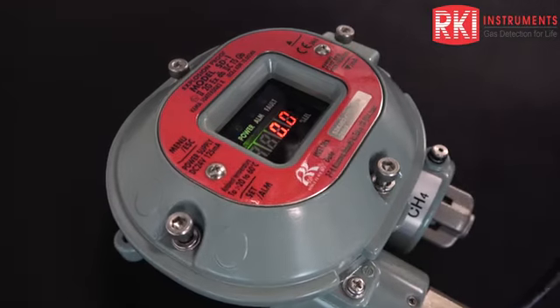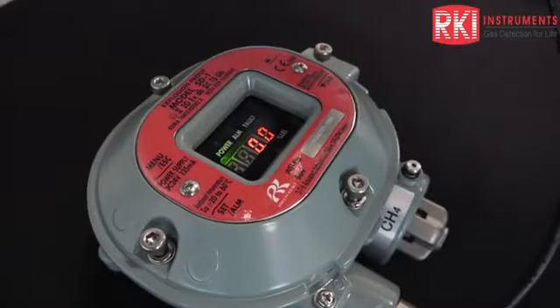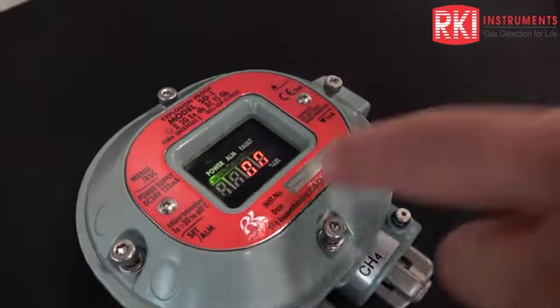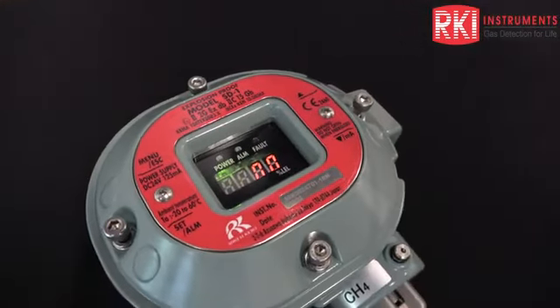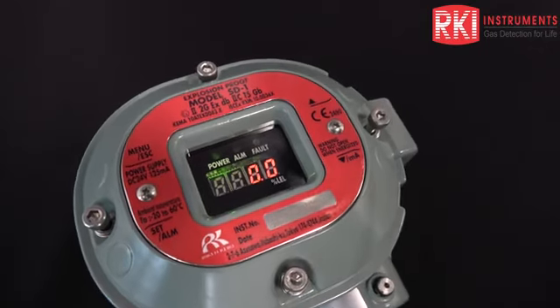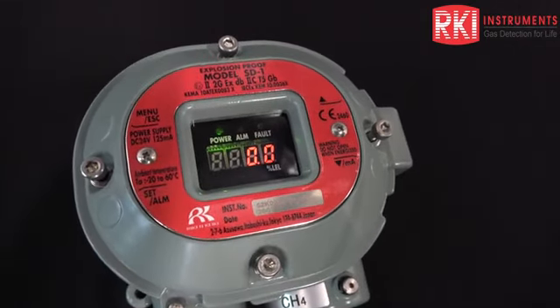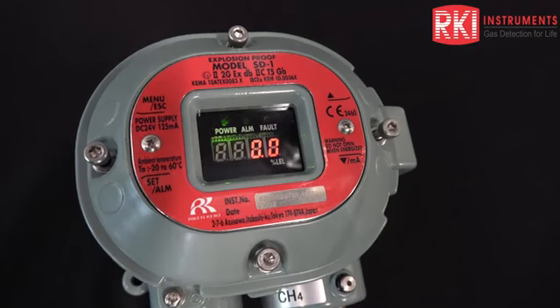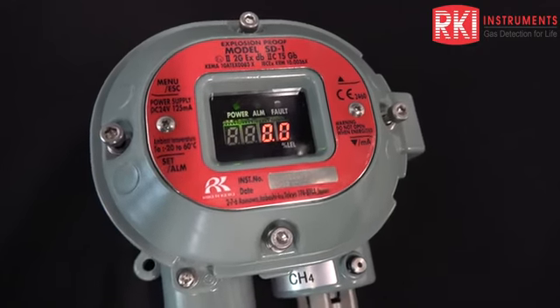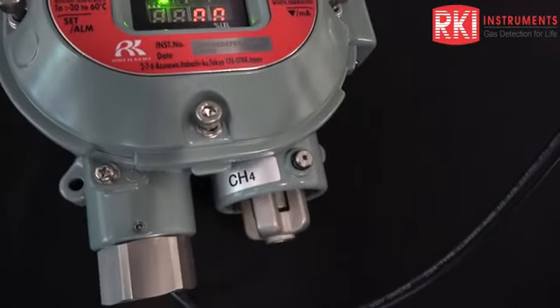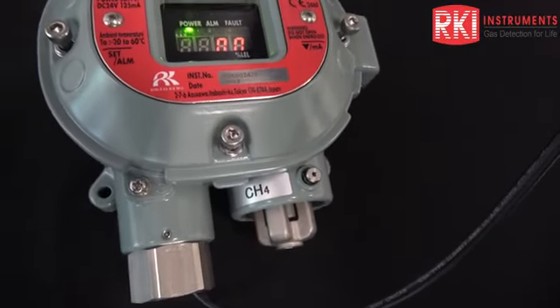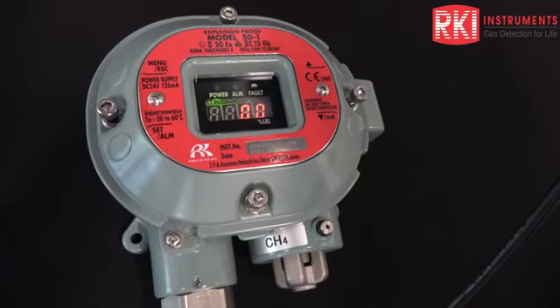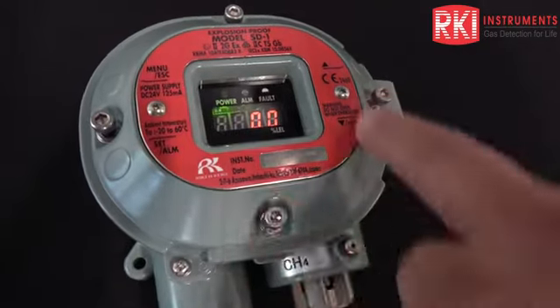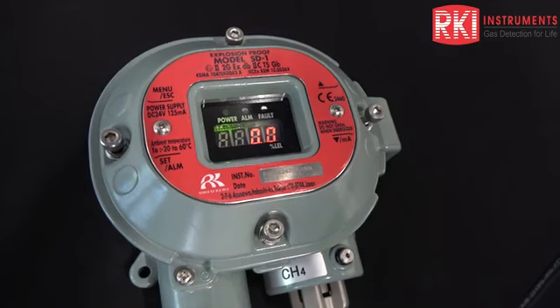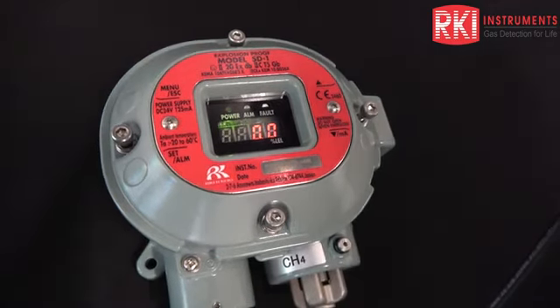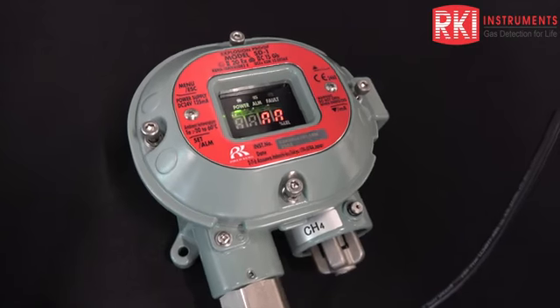So as we can see, this detector here has a red label on it, basically around the perimeter of the display. And that signifies that it's an LEL range, or lower explosive limit range detector. We also have a ppm level detector, which uses a different type of sensor. This is a catalytic type sensor in here presently, and the ppm range would use a MOS or metal oxide semiconductor type sensor. And then the label here would be yellow instead of red. So right away you can tell what kind of a range of detector you have just by the color of the label. Red would be LEL and yellow would be ppm.